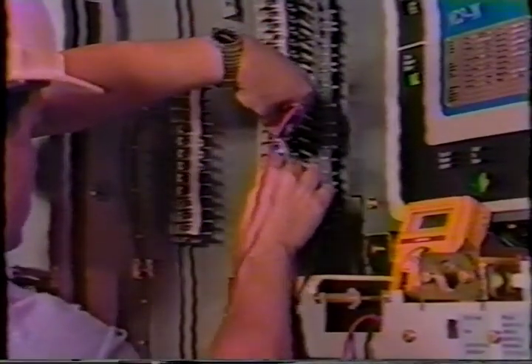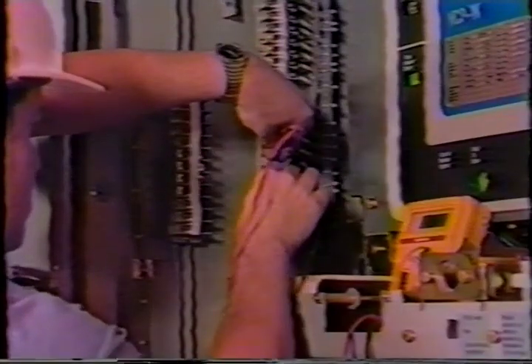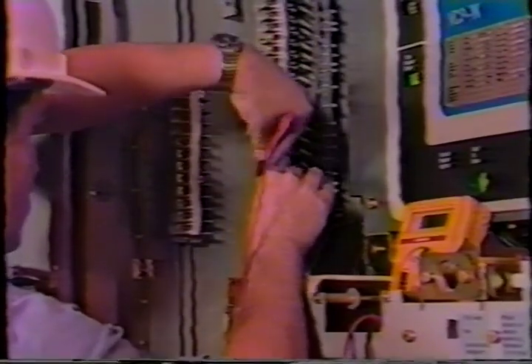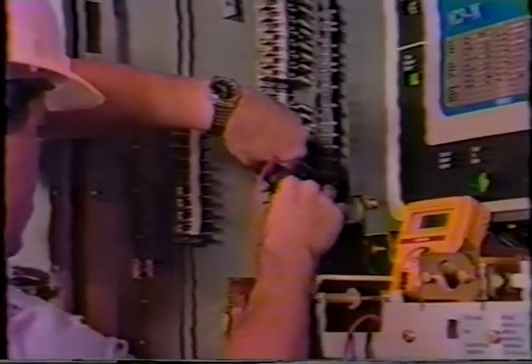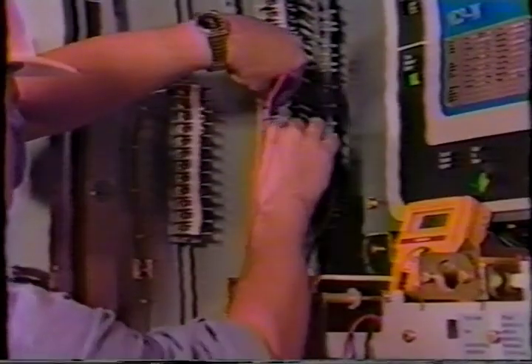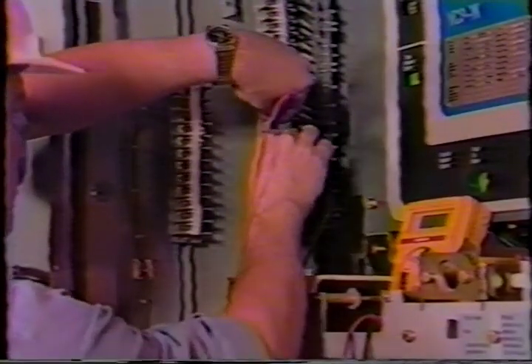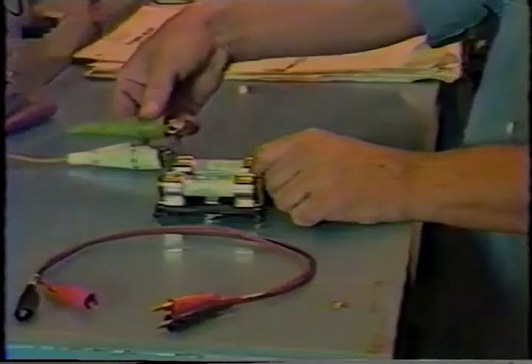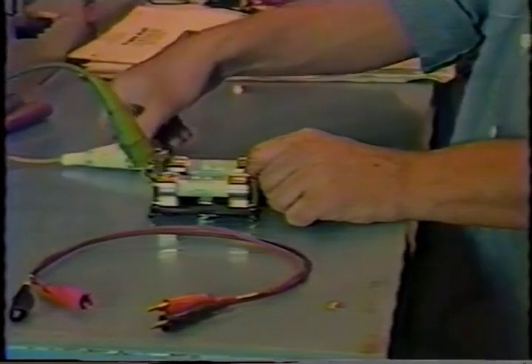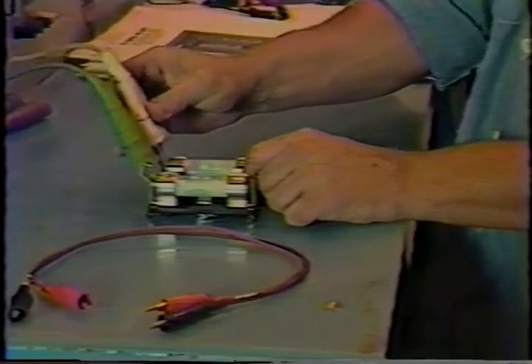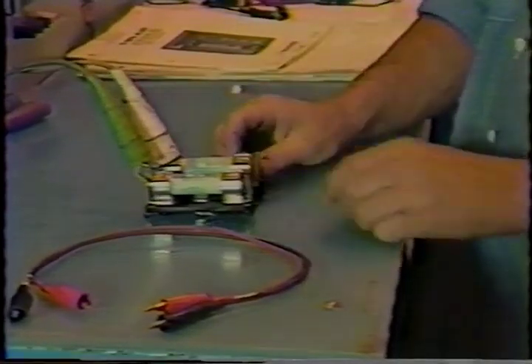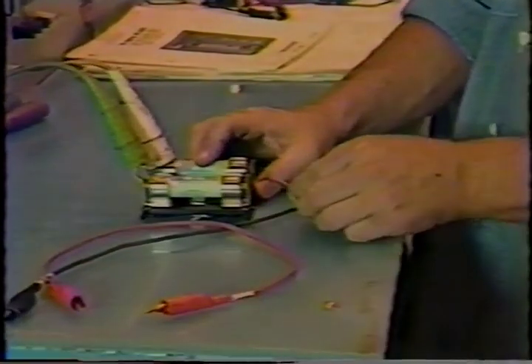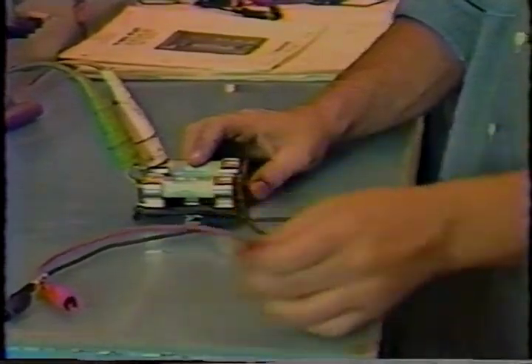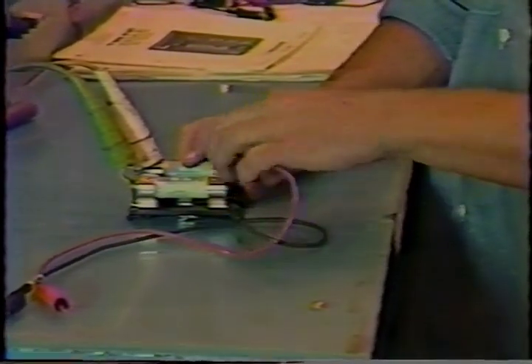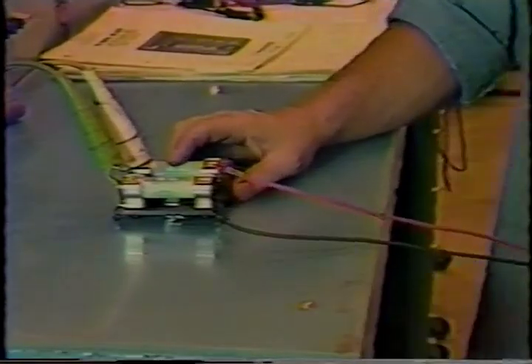Before energizing the control circuits, check the control bus with an ohm meter to make sure there are no short circuits in the control wiring. If an ohm meter is not available, connect a small fuse in series with the source of the control power. This will protect the control wiring against damage. The fuse should be 1/4 the normal rating of the circuit.